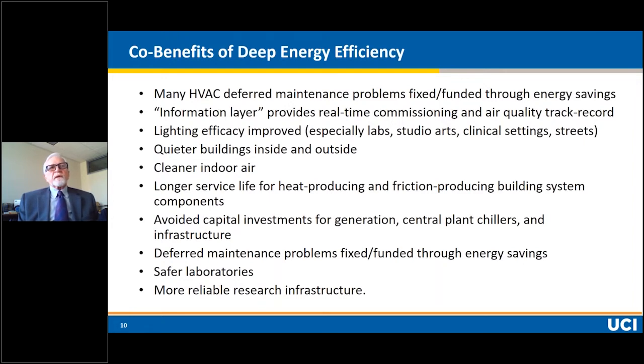Lighting quality is improved, buildings are quieter and cleaner inside. They're cleaner because we're now able to use a really high quality air filtration standard, filters just one notch short of a HEPA filter. You could never use those until you slow down the air enough that the resistance penalty of air filtration in an HVAC system goes almost to zero with the reduced air change speeds we're using. Laboratories are safer, and we have a more reliable research infrastructure.